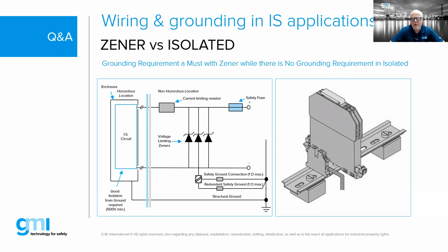Make sure it is isolated from the enclosure, because that's tied into your dirty earth. So that's a typical installation where you might find the Zener barrier mounted to a DIN rail, which in turn is tied into a ground conductor, and that is your clean earth.